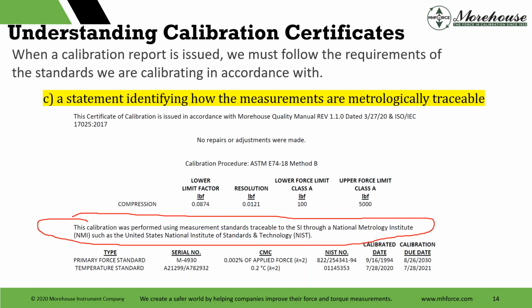Why do we say this? Because on our torque certificates, we're traceable through NPL. We're not traceable through NIST, because NIST does not do torque. And it is essential to have a chain of traceability in which uncertainty is propagated correctly. However, traceability is not to NIST. A lot of people like to say NIST traceable. That is wrong. You can easily correct that.